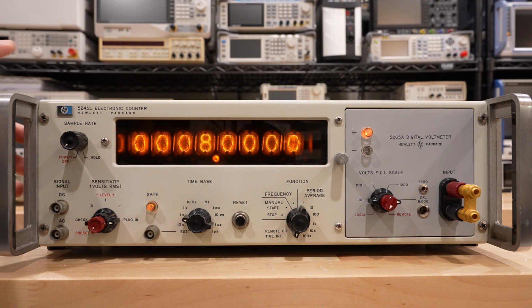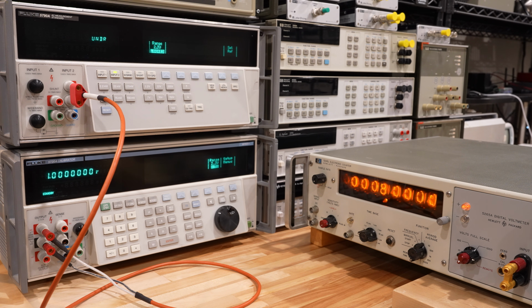But of course, this test doesn't tell us anything about the absolute accuracy of this instrument because we're only validating it against its own internal reference. In order to truly test it, we have to check it against the real calibrator. So let's do that next. So now let's use some serious calibration instruments to validate the performance of our frequency counter with the Voltmeter plugin.